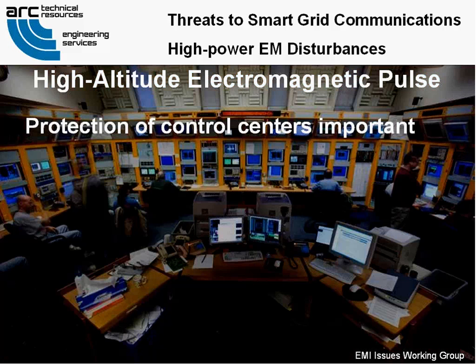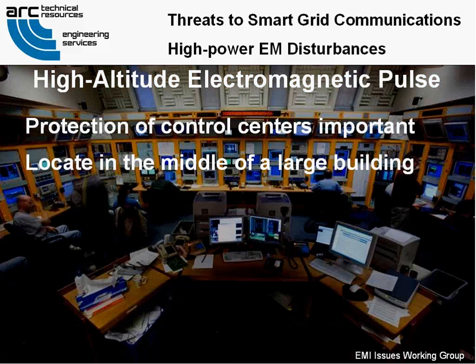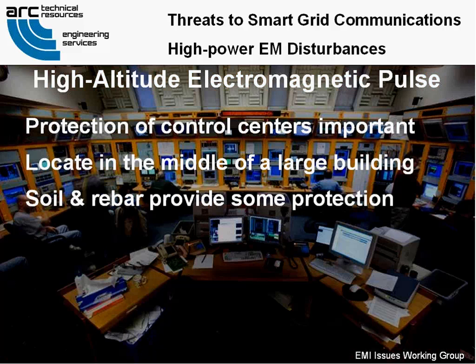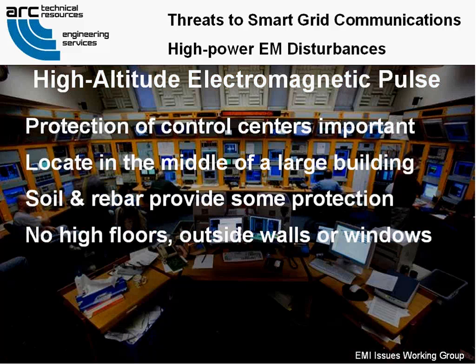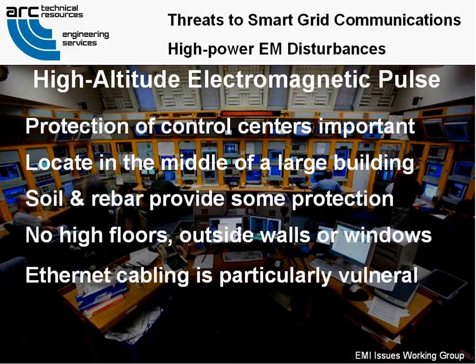The protection of control centers is becoming increasingly important. While there is great variability in the shielding effectiveness of various building types, the best approach to avoid E1 HEMP coupling is to place the control center in the middle of a large building on a low floor or in the basement, away from the windows. Soil and rebar in concrete provide some protection from high-frequency E fields. Avoid locating a control room on a high floor or near walls or windows, as the penetration of the field will be greater. Ethernet cabling is particularly vulnerable to pulsed electromagnetic fields, so consider replacing it with non-conductive fiber.